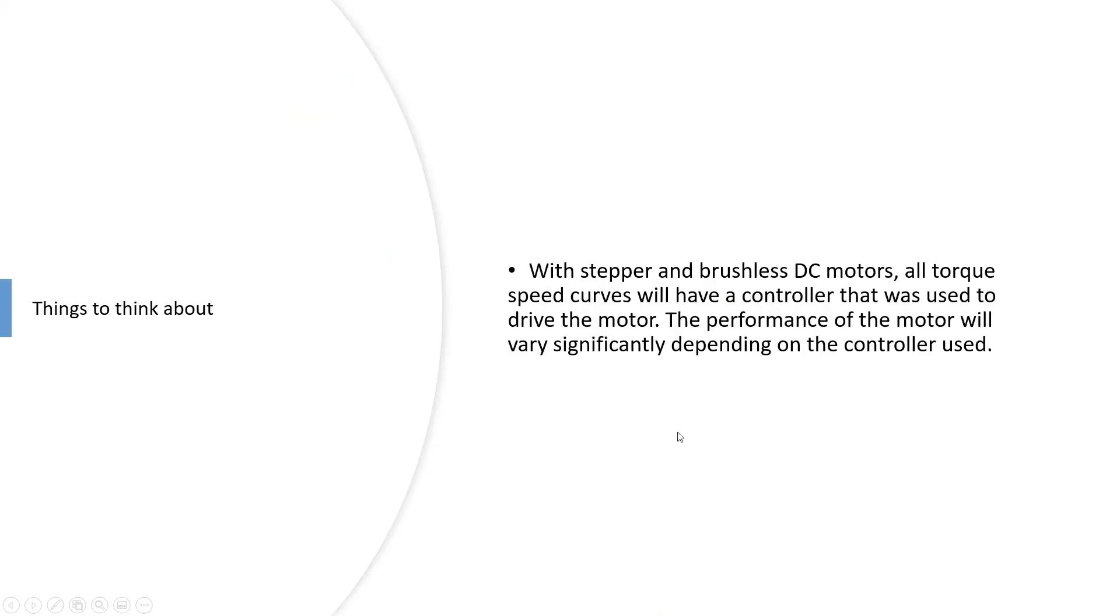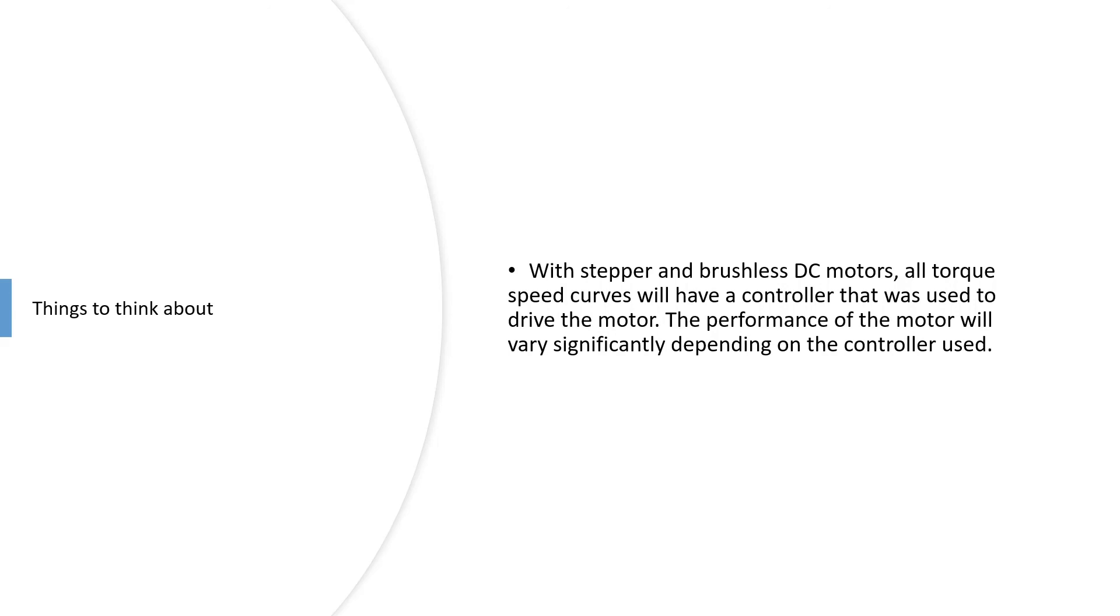The other thing to bear in mind is that stepper and brushless DC motors in particular are done using a given controller. You do need to just check that, because for example it's quite common that the motor itself will actually be able to deliver more torque or speed than it is showing in the graph if it was used with a different controller.